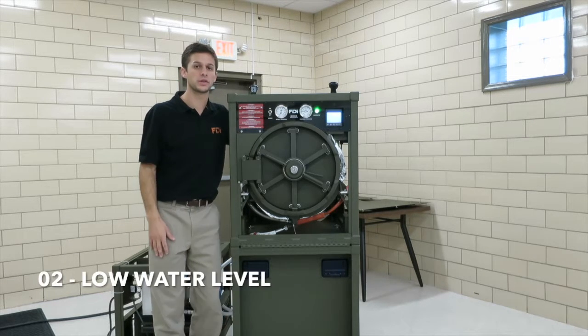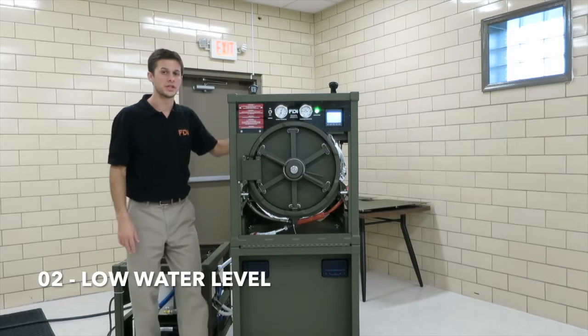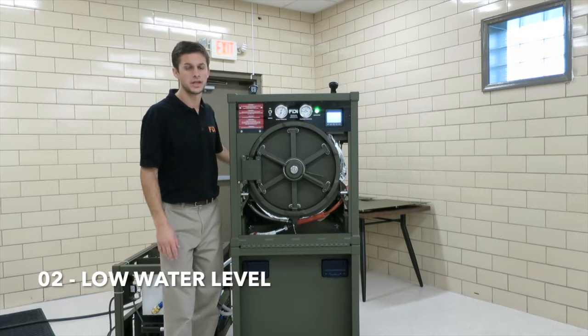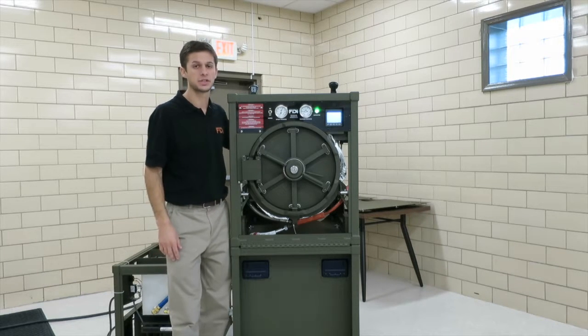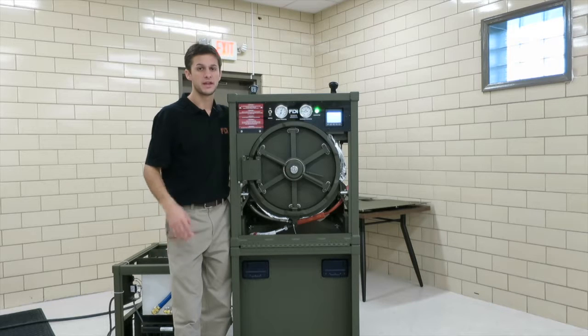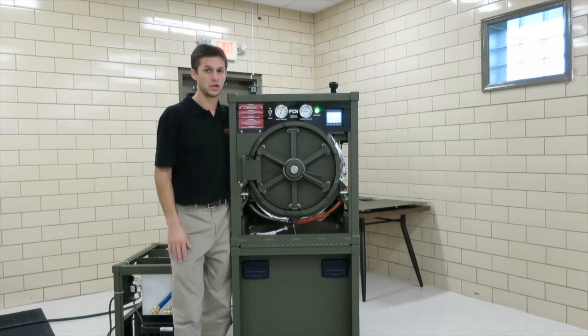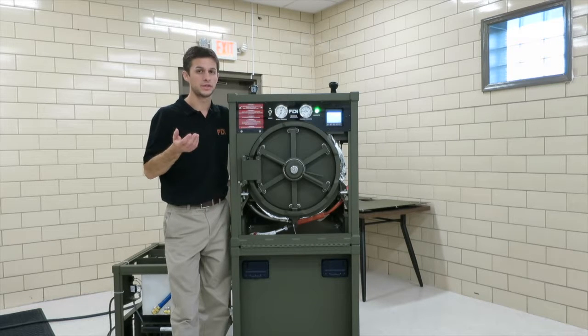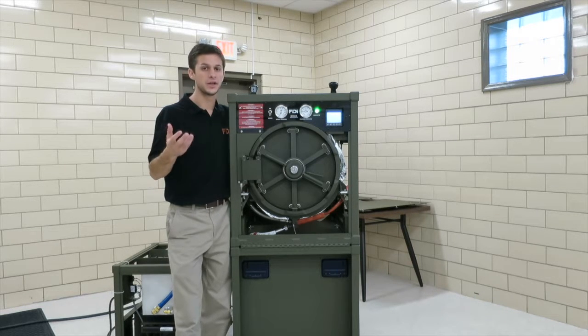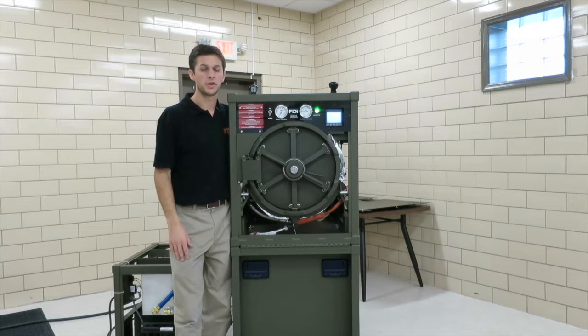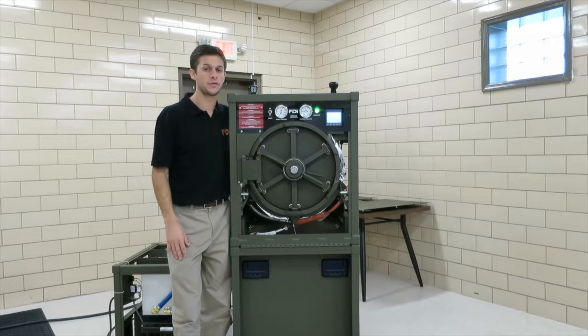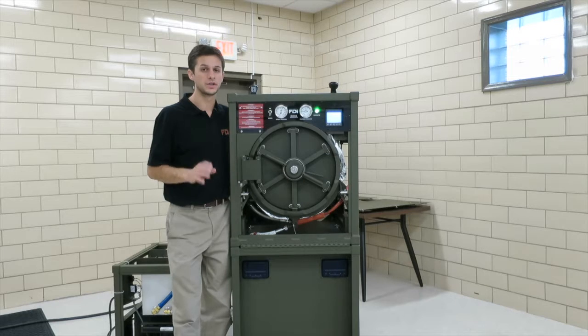02 is a low water level alarm. The liquid level switch in the back that is attached to the jacket, if water ever gets below a certain point, you're going to throw this alarm. Again, like we said, that's to protect the heaters. If the water level ever gets too low, that alarm is going to go off and turn off the heaters so they don't burn up.